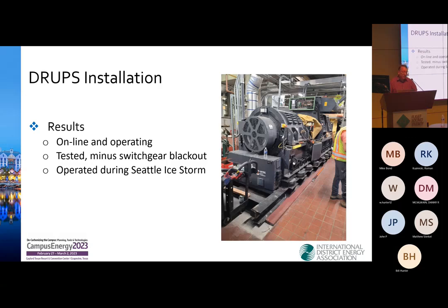Once it was online and operating, we tested it using a load bank up to 2 megawatts for about 6 hours, did all kinds of trip testing. But when it came time for them to ask, okay, let's disconnect the plant from utility and see if the DRUPS works, well, this was December, we're in high heating mode. So I hesitated and said, no, we'll take our chances, I'll trust that you guys know what you're doing.